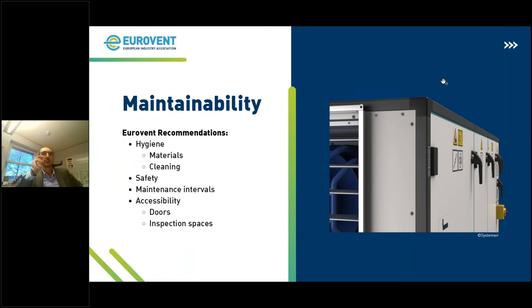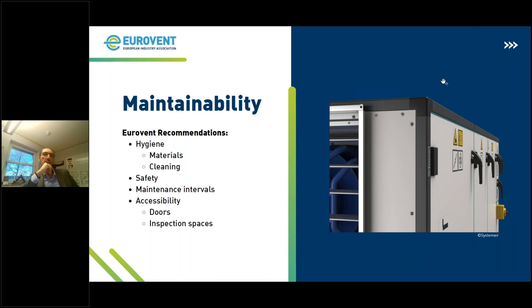In this paper, recommendations for maintainability are explained across some important aspects: hygiene, safety, maintenance intervals, and very importantly, accessibility. Hygiene as a general topic is explained in section 112 of the document. The materials should be resistant to abrasion, emission-free, and microbially not metabolizable. It is recommended to use metallic materials in the airflow as much as possible — avoid plastic, but if plastic is used, it must be ISO 846 compliant against fungi and bacteria reproduction.